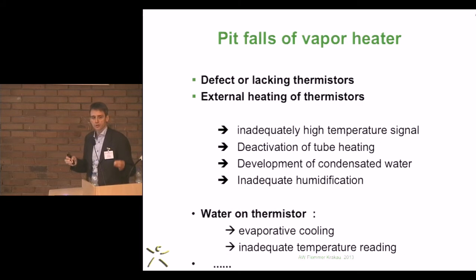So as a result, what you should be aware of is keep the thermistors on top of the tubing, and if they are wet, dry them out in order to have right readings. And again, you can control that by just measuring the water consumed by the humidification device. Look at the development of condensed water and be aware of what I just said with the thermistor that is wet.